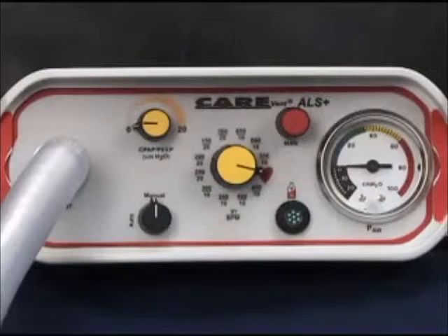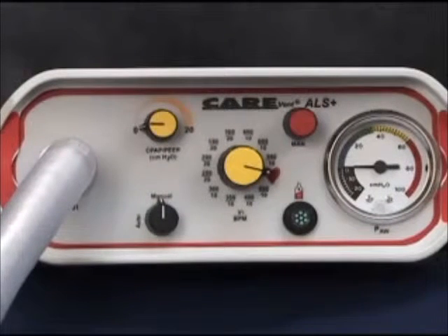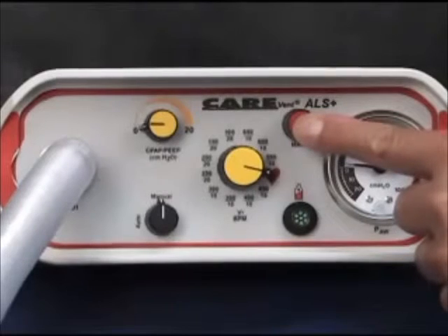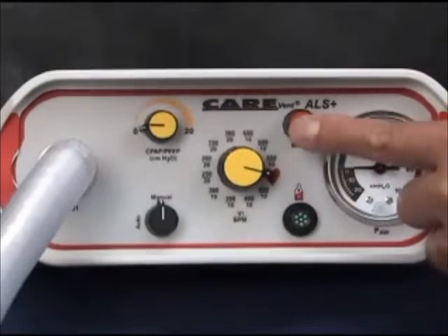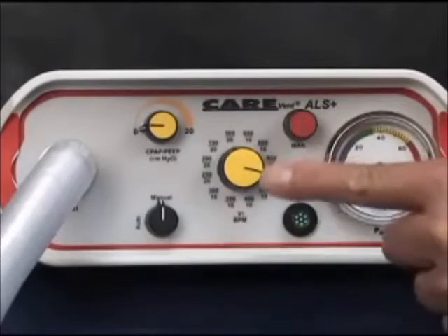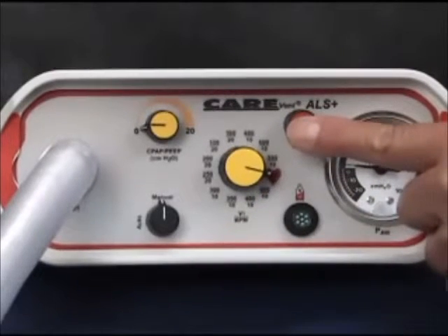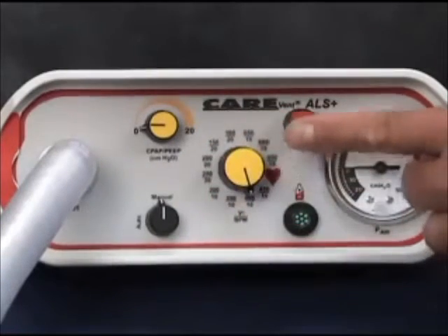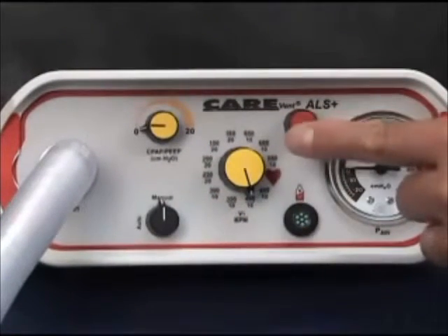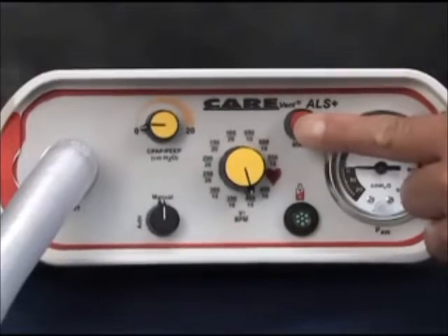The range extends from small children to large adults, and all settings are calibrated in line with the current resuscitation guidelines. The manual position will allow the operator to provide manual ventilations using the manual override button. These manually actuated ventilations can be used to support a patient in respiratory distress, or to provide manually triggered ventilations to a non-breathing patient. The flow rate provided by the actuation of the manual button is equivalent to the pre-selected automatic setting on the rotary setting selector control.